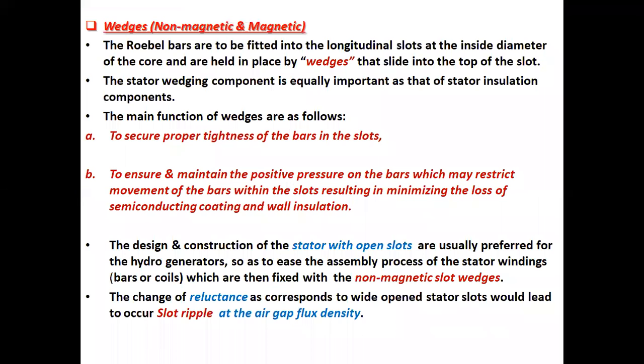Wedges, non-magnetic and magnetic. The roebel bars are to be fitted into the longitudinal slots at the inside diameter of the core and are held in place by wedges that slide into the top of the slot. The stator wedging component is equally important as that of stator insulation components. The main functions of wedges are as follows.